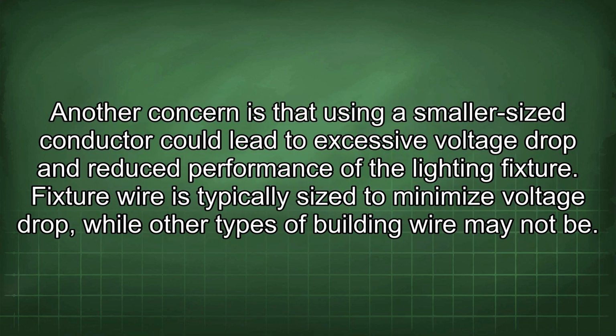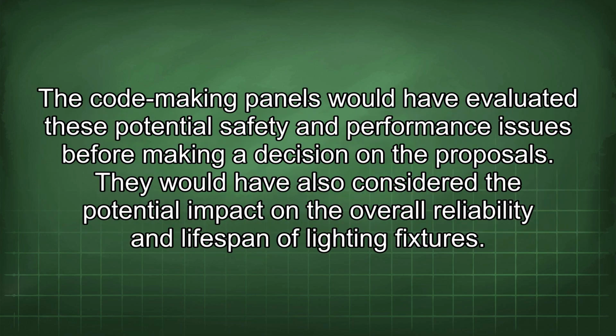Another concern is that using a smaller sized conductor could lead to excessive voltage drop and reduce performance of the lighting fixture. Fixture wire is typically sized to minimize voltage drop, while other types of building wire may not be. The code-making panels would have evaluated these potential safety and performance issues before making a decision on the proposals. They would have also considered the potential impact on the overall reliability and lifespan of lighting fixtures.